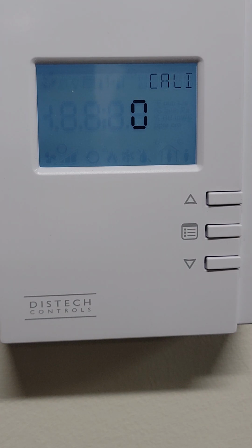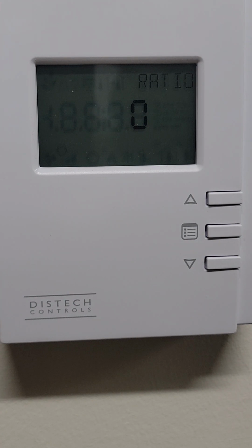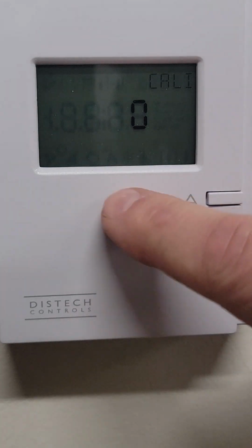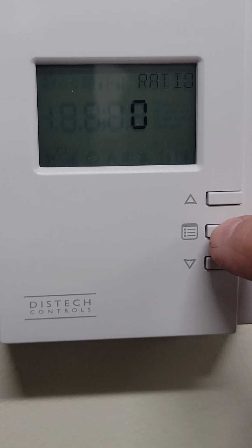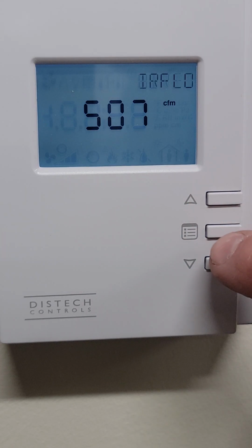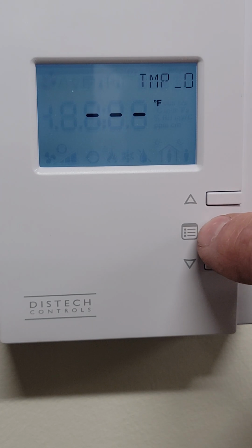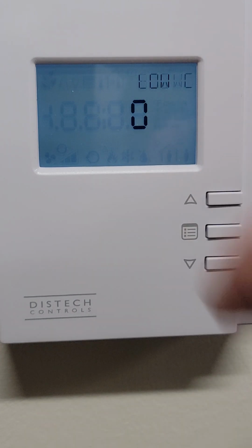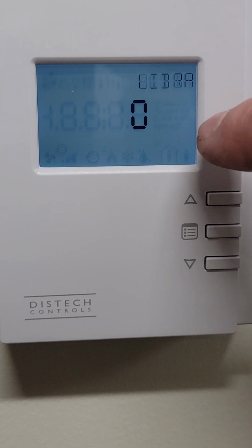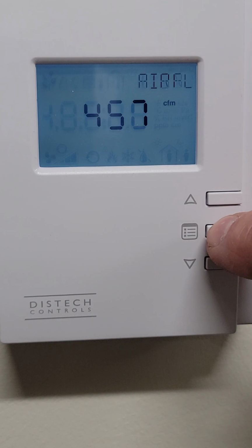The flow calibration is where you would put in the total flow that you've measured using your hood. If you have 4 diffusers and you measure 100 CFM at each diffuser, you would enter the total, in this case 400 CFM, in this flow calibration value. The thing to remember is you'll enter the value, but the next time you roll through it, it will return back to 0. So don't expect this number to stay at what you put it in.